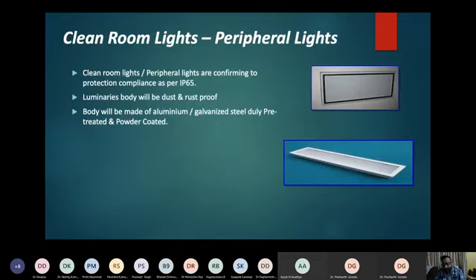Coming next to the clean room light peripherals - normally 2 feet by 1 feet lights are used, and the luminosity of this light is designed by the designing team as per the IP65 standard. There is a standard when you say 10 by 10 or 15 by 15 OT when designing, for where these peripheral lights should be. We need to fix what size of light should be there and what the luminosity of this one is. Normally it varies from 1100 to 1600 lumens, depending on the size of the room and the size of the lights.